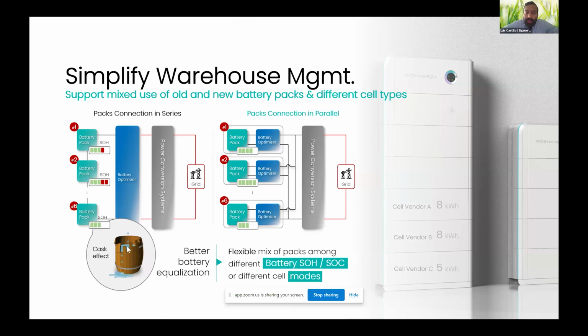Another advantage of our solution is that every single battery pack has its own dedicated battery optimizer, built inside the battery pack. This helps the battery packs work at different states of health or state of charge. This is why we can mix 5 kilowatt hour with 8 kilowatt hour battery packs in the same stack, mix old and new batteries, or mix a fully charged battery with a fully discharged one. We could even have different cell technology inside different battery packs, since they are completely independent.